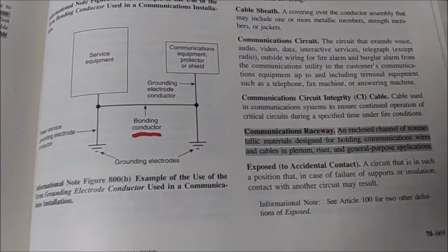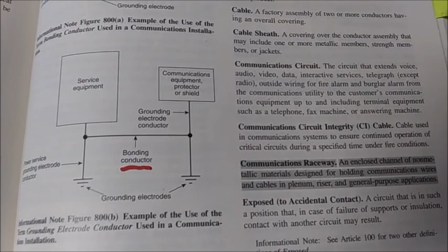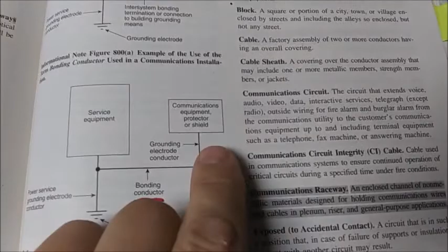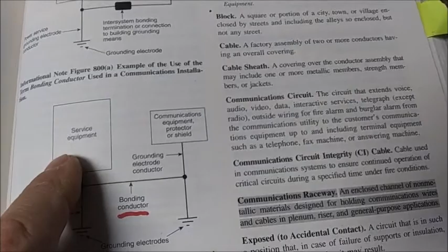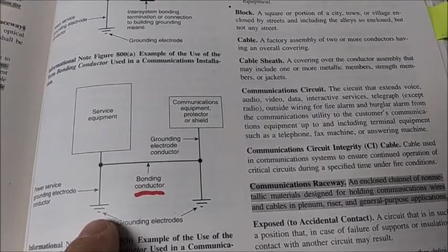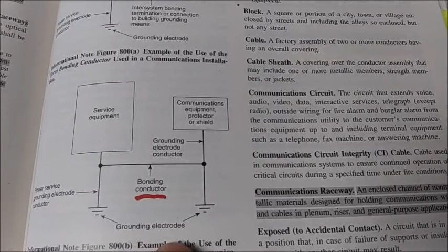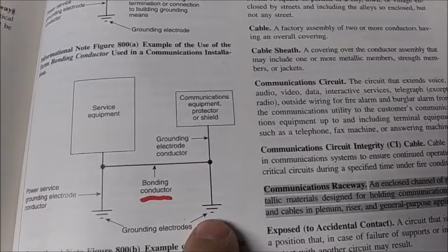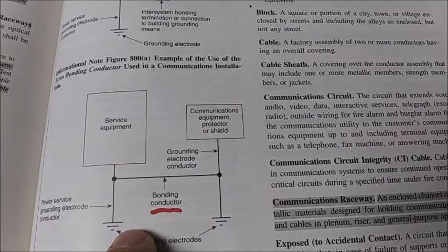along with the 3 feeder conductors. But what's critical in this diagram is to understand that there must be a bonding conductor between the communications equipment on the right and service equipment on the left, and service refers to commercial power service. There's a ground at the service entrance. See? Power service, grounding electrode conductor. And the code here presumes that the communication system also has the ground, and it is absolutely mandatory to have those 2 ground rods properly bonded together, else it is a gross code violation and dangerous.